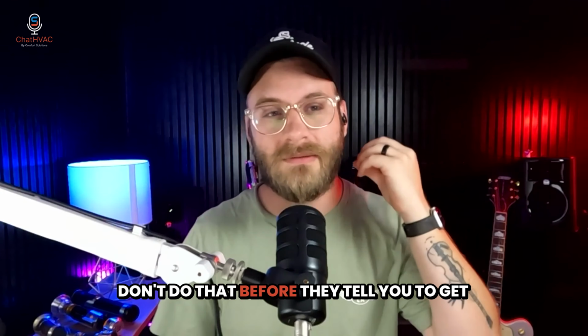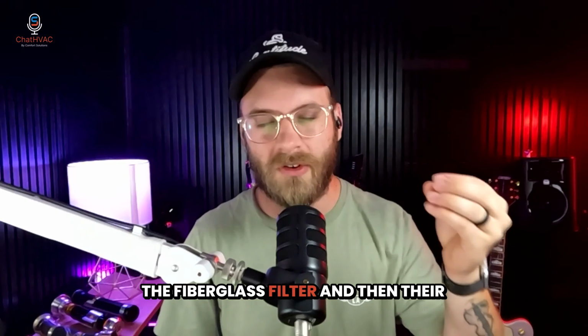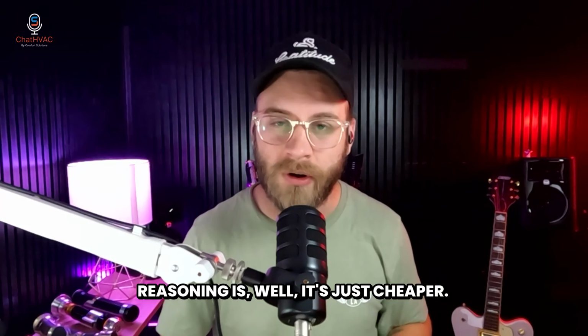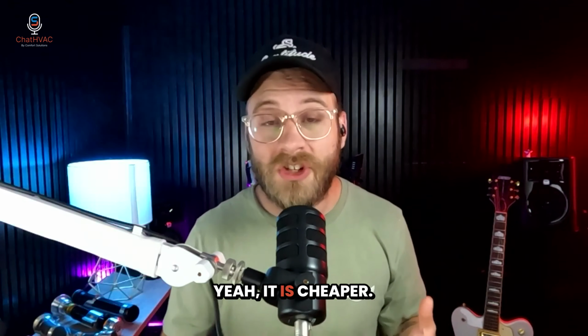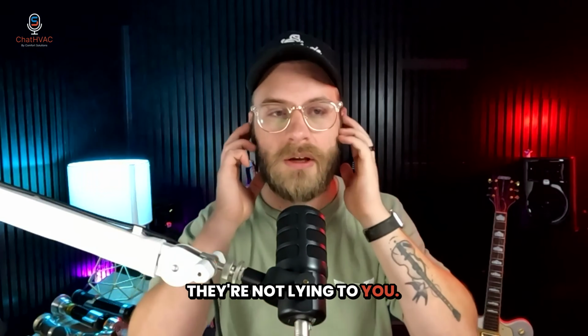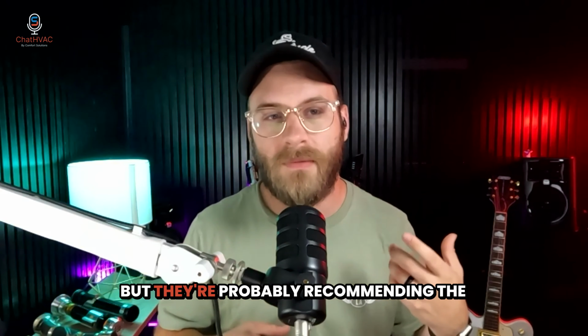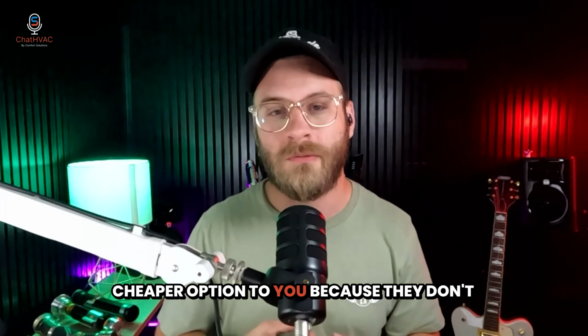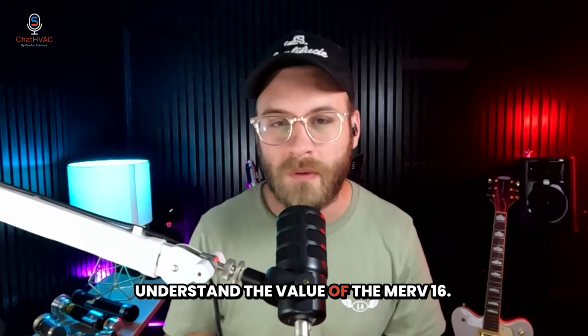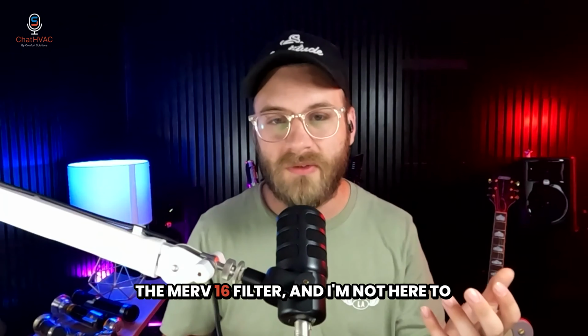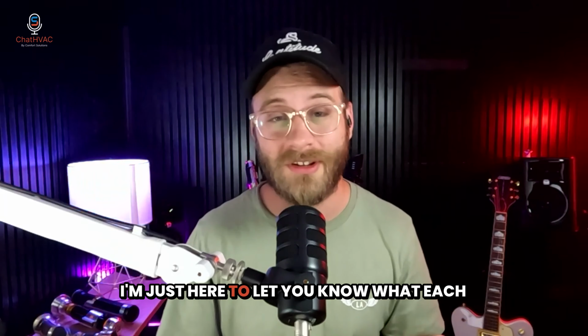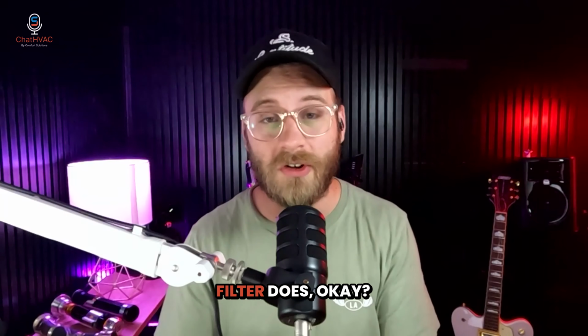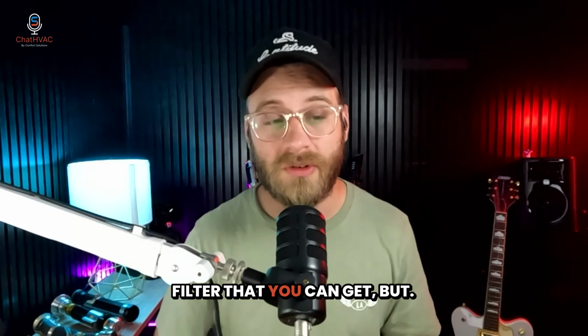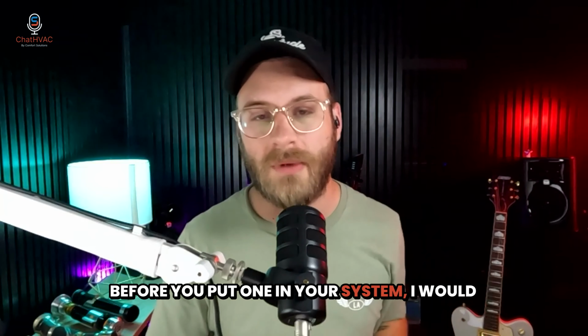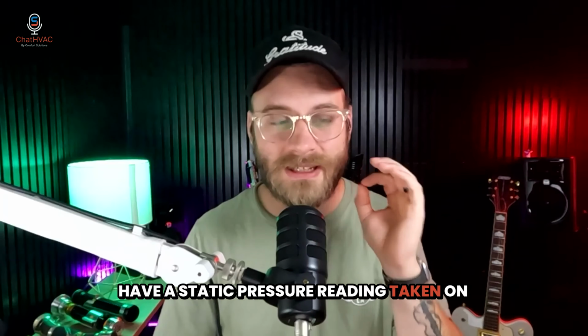Don't do that. Before they tell you to get the fiberglass filter with reasoning that it's just cheaper, don't listen to them. Yeah, it is cheaper, they're right, they're not lying to you. But they're probably recommending the cheaper option because they don't understand the value of the MERV 16. I'm not here to sell you filters, I'm just here to let you know what each filter does. The MERV 16 filter is probably the best filter you can get, but before you put one in your system, I would have a static pressure reading taken.